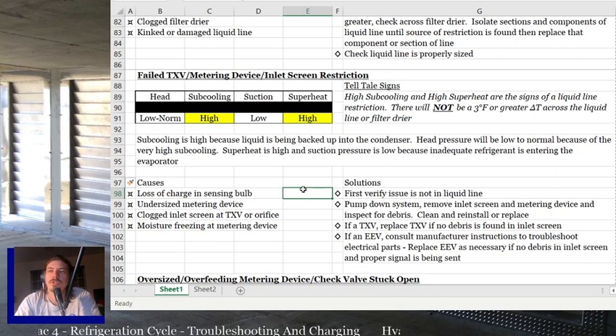If you have moisture traveling in the system and you've got no filter dryer, you've got basically droplets of moisture traveling through the system. They can freeze up right at the metering device and make it look like a liquid line restriction. Just keep that in mind, but usually you'll see other things that will tell you it is not the metering device, that it's moisture. The solution is first verify the issue is not in the liquid line, pump the system down, remove the inlet screen and the metering device, and inspect them. Clean and reinstall or replace.